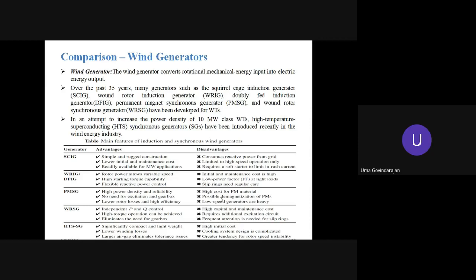And the last one is the high temperature superconducting synchronous generator. It is significantly compact and lightweight, because the aim of the construction is to increase the power density. So obviously, it will be lightweight and compact, with lower winding losses, and a larger air gap eliminates tolerance issues. Disadvantages: high initial cost, complicated cooling system design, and a greater tendency for rotor speed instability.